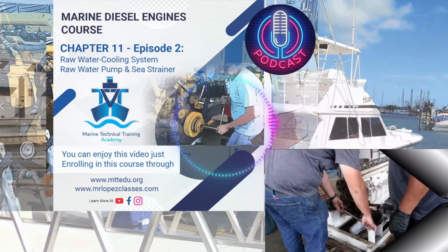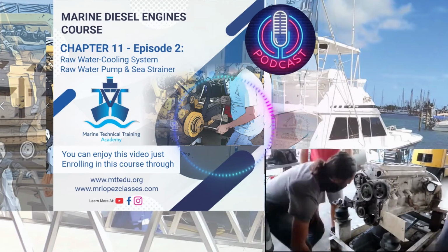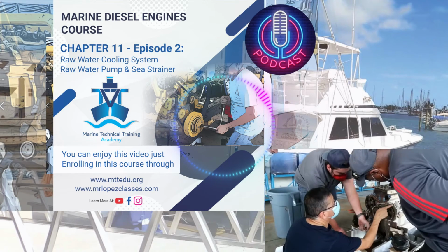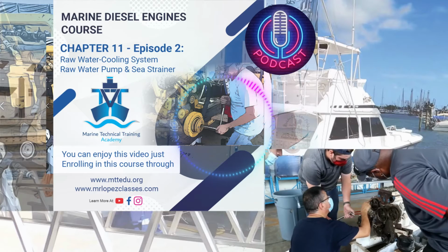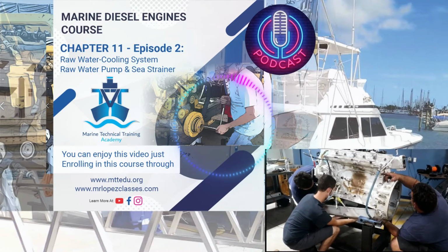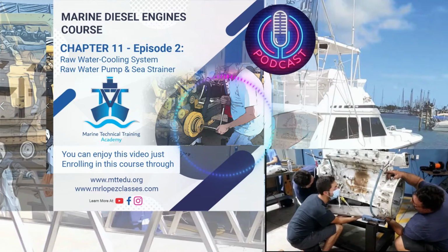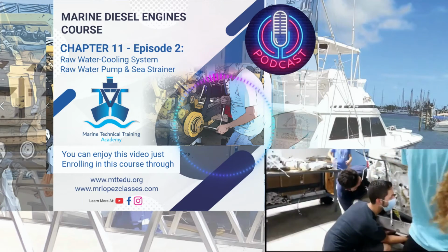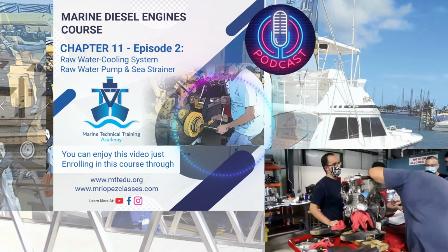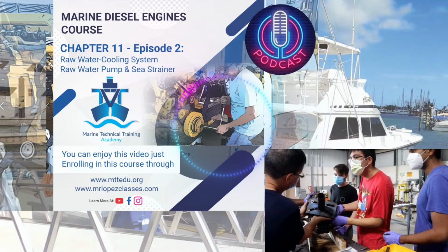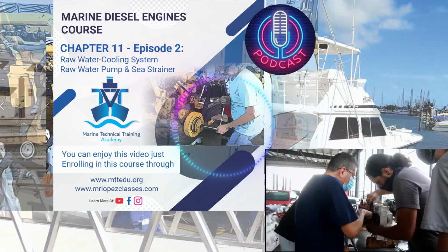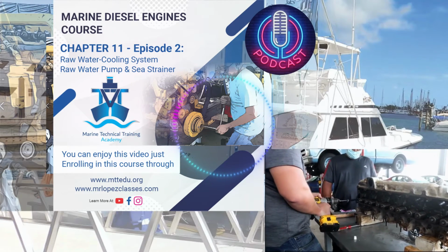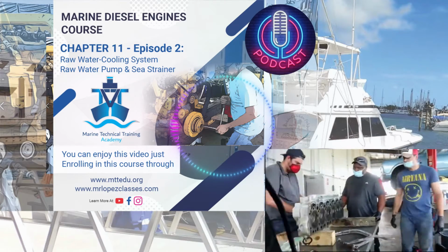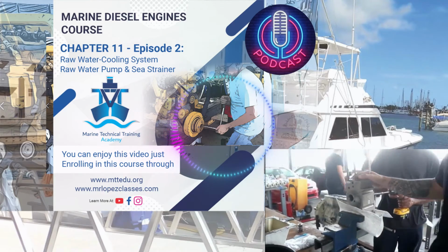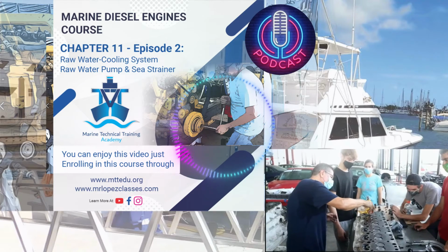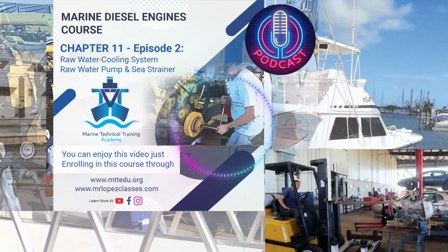Okay, one important element in those engines with the circulation of raw water is the raw water pump, and the strainer, the sea strainer. And we are going to study in this chapter in detail what happens with the raw water pump. We are going to disassemble the raw water pump, and we are going to study it, and we are going to try to understand the procedure to do the service in a typical raw water pump. We are going to replace the impeller, and we are going to recover the raw water pump. The same with the strainer. We are going to open the strainer, clean the strainer, and check all the information related to the strainer.